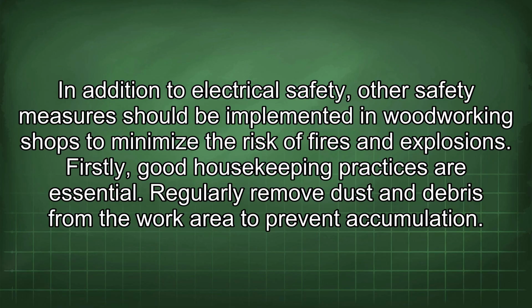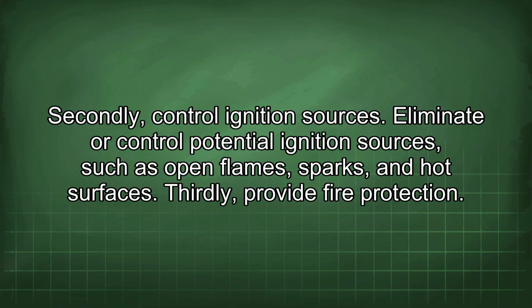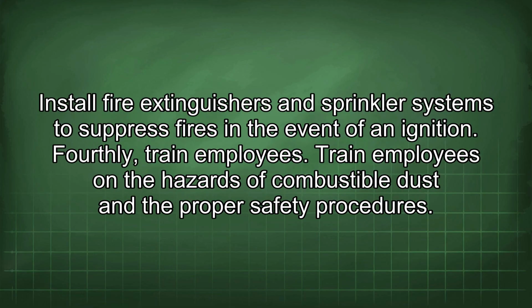Firstly, good housekeeping practices are essential. Regularly remove dust and debris from the work area to prevent accumulation. Secondly, control ignition sources. Eliminate or control potential ignition sources, such as open flames, sparks, and hot surfaces. Thirdly, provide fire protection. Install fire extinguishers and sprinkler systems to suppress fires in the event of an ignition. Fourthly, train employees. Train employees on the hazards of combustible dust and the proper safety procedures.